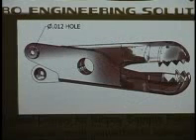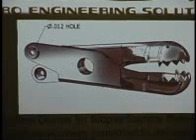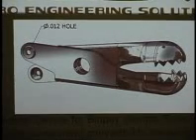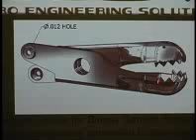Some people might be familiar with this, biopsy forceps. Nobody ever wants to have this done, but it's nice to know that these are very accurately stamped and sometimes molded. These particular ones are 12 thousandths holes, and the teeth are 7 thousandths high. So you can imagine the stamping die that had to make these. And I've actually had molded parts. I can't show those, but those are the same size, 7 thousandths high teeth.